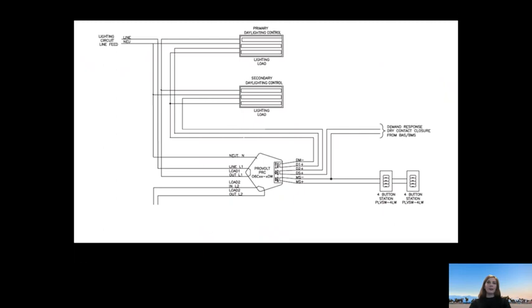To further understand the simplicity of the Provolt system, here's a schematic of the PRC06C model. We have our singular line voltage connection to the Provolt PRC unit. From the unit, we have 2 loads. Load 1 being a line voltage 120 volt connection to the luminaires, and load 2 being a low voltage signal that goes to a power pack to control your desired HVAC or plug loads. On the low voltage side of the PRC, we have our 2 dimming channels to the luminaires, a primary dimming and secondary dimming for dual zone dimming applications, as well as a demand response input and our main input that is a low voltage signal from our desired switches.